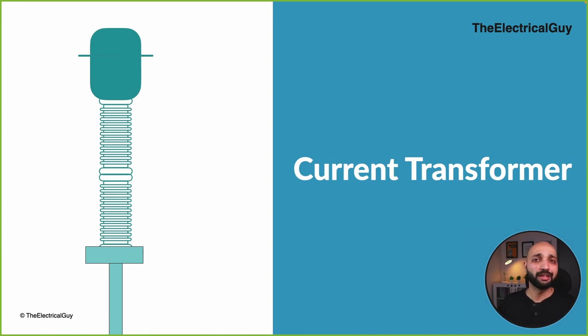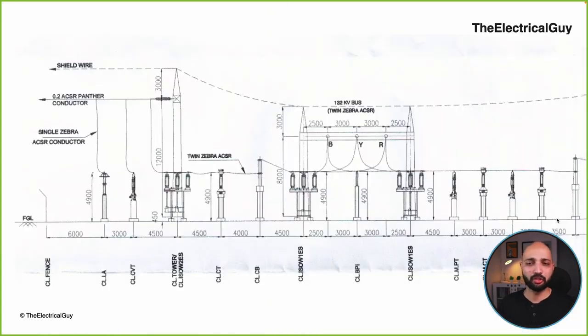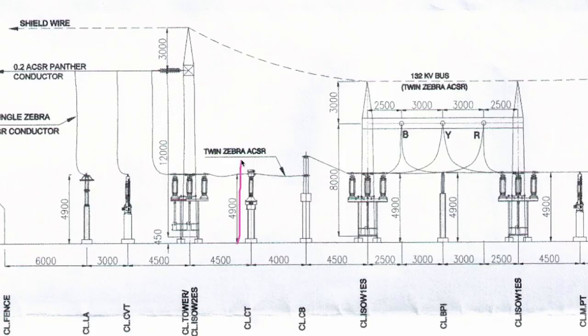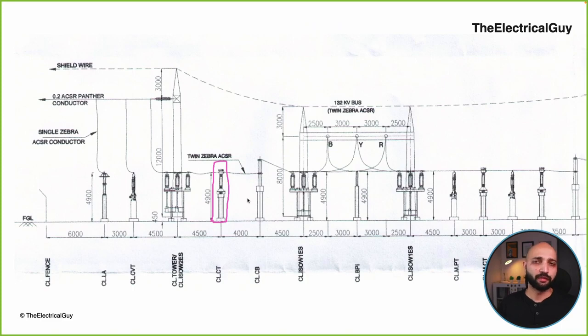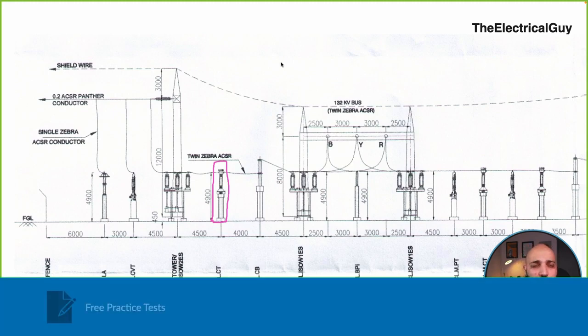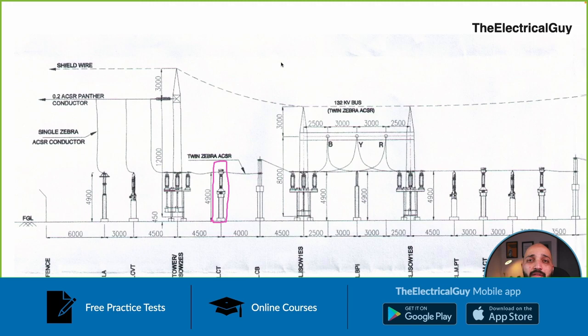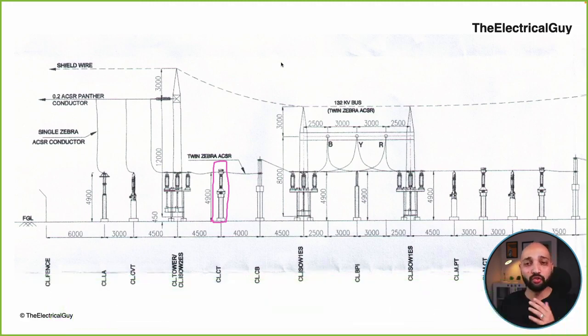Now moving on, let us talk about the next device that we have in the substation, and that is the current transformer. So here you can see this is the current transformer. Now what is the function of a current transformer? Again, the current transformer is one of the instrument transformers. Now the current ratings that you will see in a substation generally range from 1250 amperes to maybe 2000 ampere, 2500 ampere, and in some cases it can go up to 4000 ampere depending upon the voltage rating.